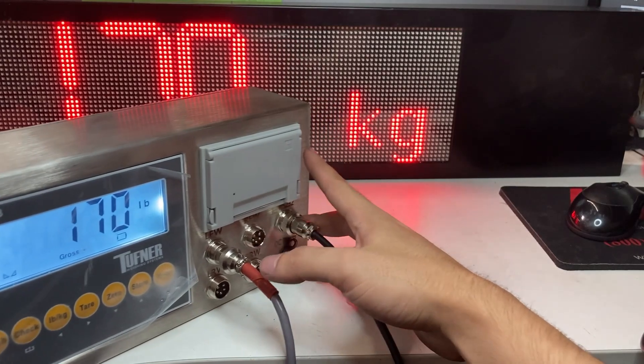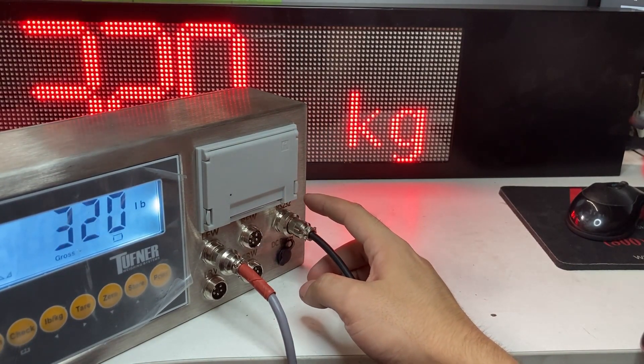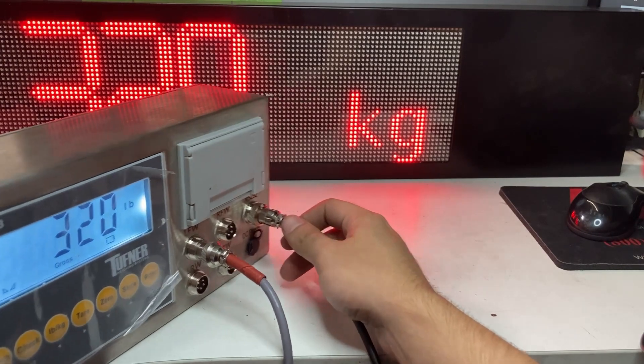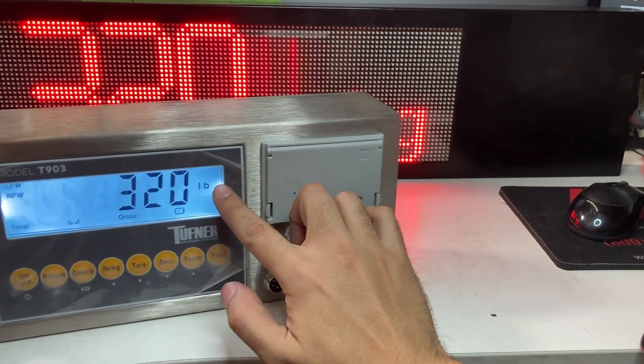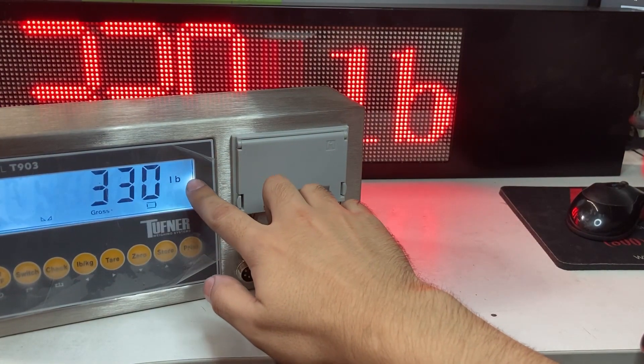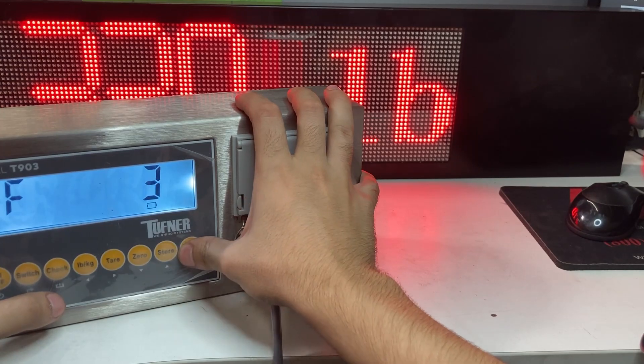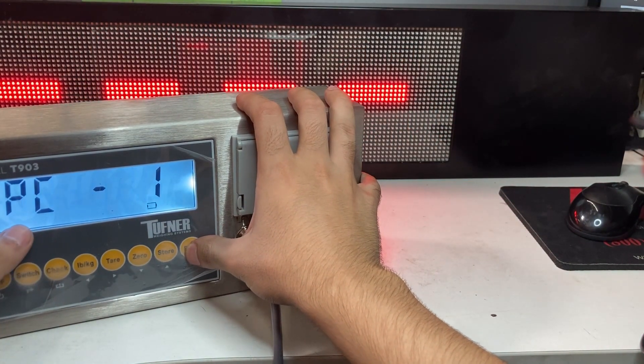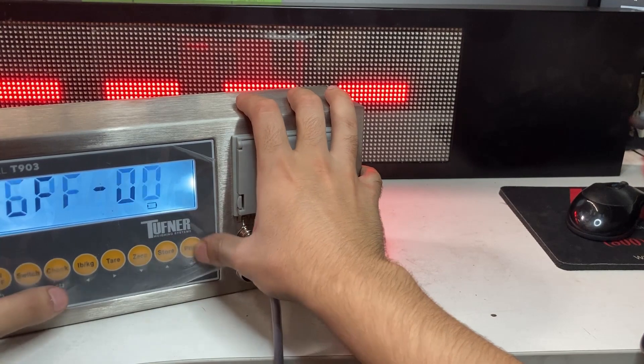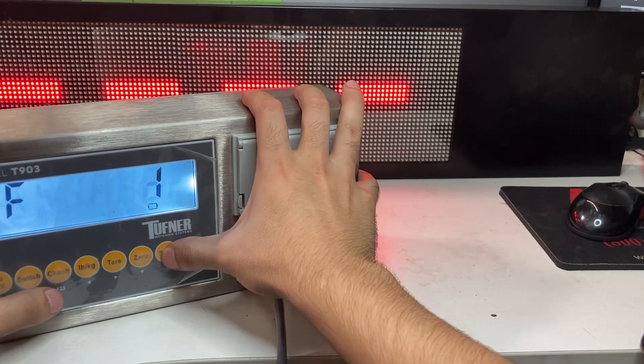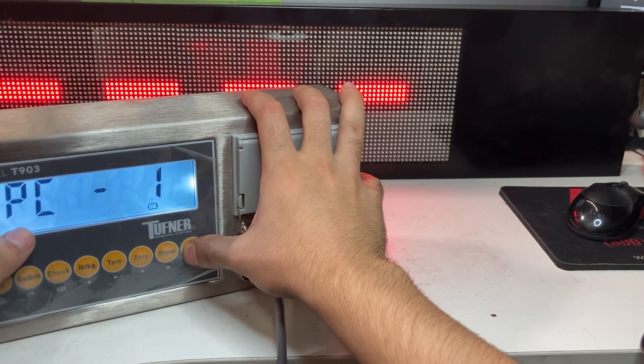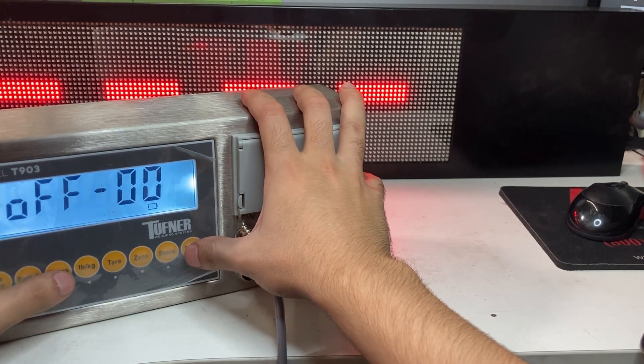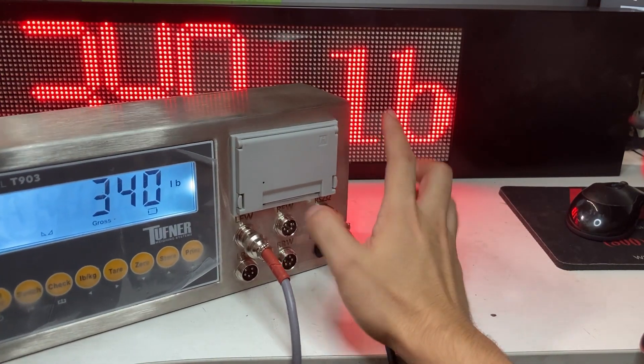Now you can see 170. Right now, it's KG. It says pounds. So you will see a problem where the weight corrects, but it says KG here but pounds here. I was able to get it to show the pounds correctly. So what I've noticed, sometimes I have to go to PC, make it zero, disable it. And then go back to F3. Go back to PC and make it to 1 for a continuous setting for a PC. And now it's showing properly 340 pounds.